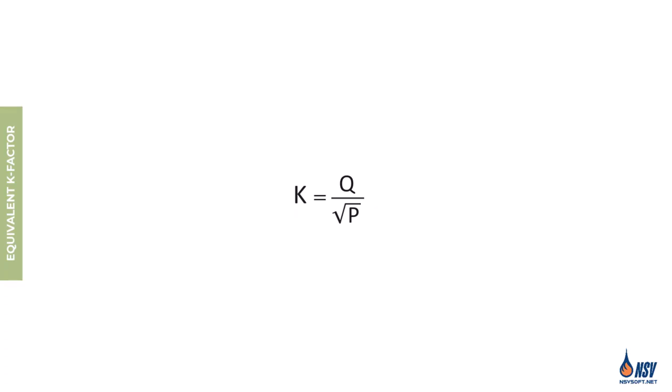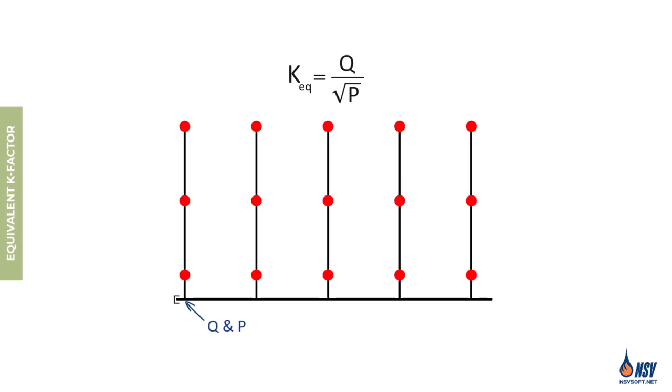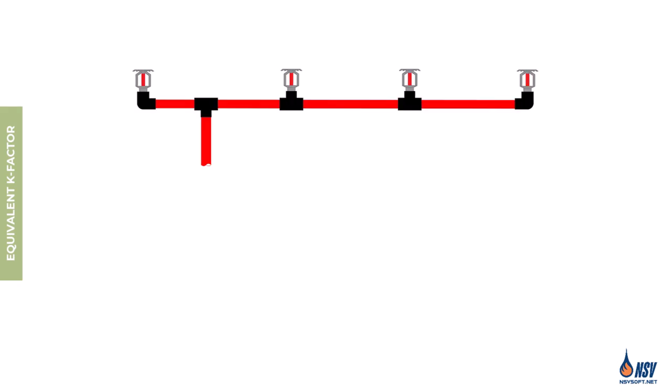Although we've discussed the K factor of individual sprinklers, the same concept can be applied to a section of the system. Whenever we know the flow rate and pressure at a certain point, we can calculate the equivalent K factor for the downstream portion of the system. For example, a flow rate of 70 gpm at 30 psi is calculated at the exact point where the right outlet of the tee connects to the branch line serving three sprinklers.